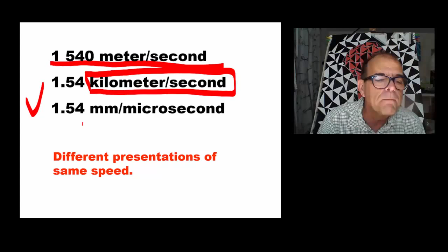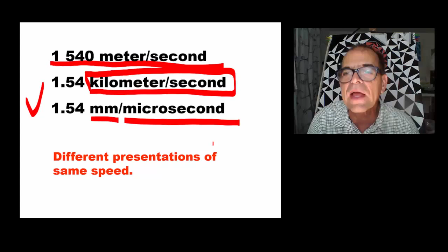And the most important is this one, 1.54 millimeters per microsecond, because this is the measure of propagation speed that is better for calculation. Sometimes in the examination you need to make some calculation about the propagation speed of ultrasound. When you use millimeters, this is more realistic in the human body than meters, because a liver cannot be measured in meters, it can be measured in millimeters, it is little.